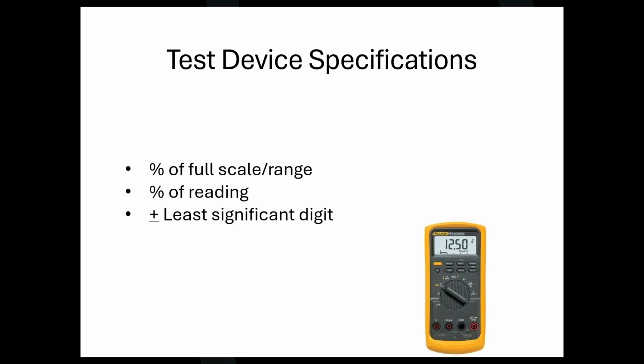You see this a lot, especially when you're doing flow, gas, and pressure measurements. So be very careful when you're looking at this stuff. I always try to stay away from test devices that say full scale or full range on them because of this, and people do not realize that.